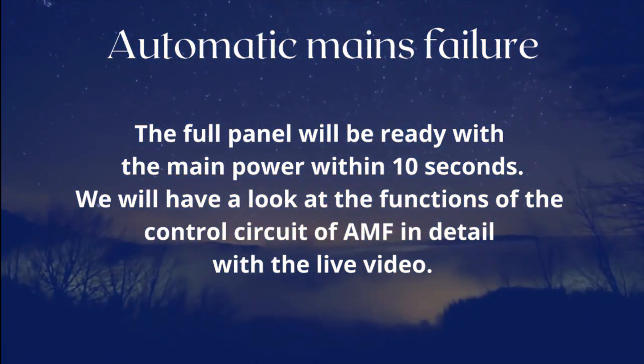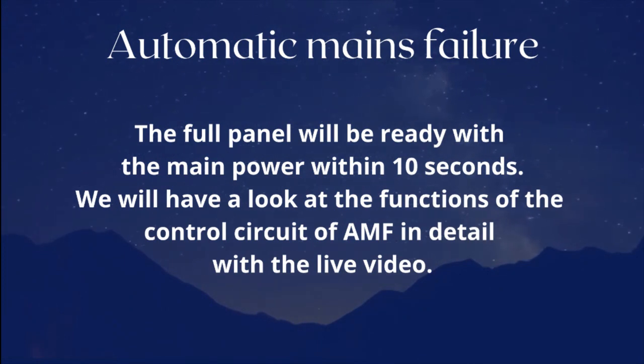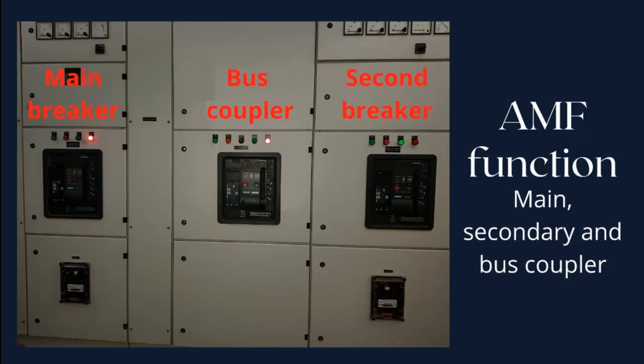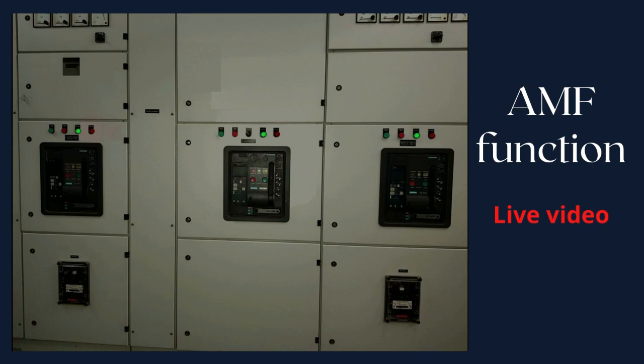We will have a look at the functions of the control circuit of AMF in detail with the live video. The function of the AMF system in a panel with main, secondary, and bus coupler: the main breaker closes with main power; main power fails; no power in the complete panel; the generator starts; power reaches the secondary side; the secondary breaker closes; main and bus coupler breakers open. When power restores, the secondary breaker opens, the main breaker closes, and after two seconds the bus coupler will close.